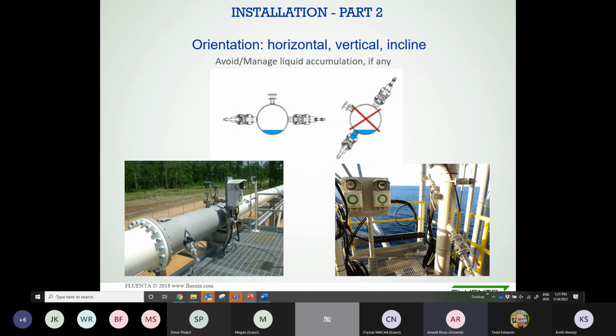If you're restricted to a vertical pipe, then there are mechanisms that we can utilize in the meter itself. It's hard to see from this picture, but we normally have a fitting here that we can use to drain the sensor, at least the upstream sensor, to make sure there's no liquid accumulation, and we can easily send that liquid back to the knockout drum. So there are mitigation factors, but when it comes to installing the meter, there are some considerations. Sometimes we've seen installations where they decide to make it a slanted installation to make sure that if there are any liquids, they will drop down the line. But it all depends on what kind of situation you have, and what kind of flexibility you have in order to install the meter.